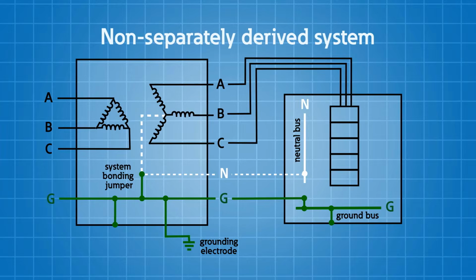Now, we've established what a separately derived system is. And we know that, especially in the case of a generator, depending upon how you bond things in the generator and whether you establish a separately derived system, that will drive the solutions that you purchase and install. A non-separately derived system, good examples of those are your downstream panel boards, or that generator that doesn't have an established neutral-ground bond in there, where you're using a 3-wire or a 3-pole transfer switch. Those are your non-separately derived systems. You're keeping your grounded conductor separate from your equipment grounding conductors in all of those locations.